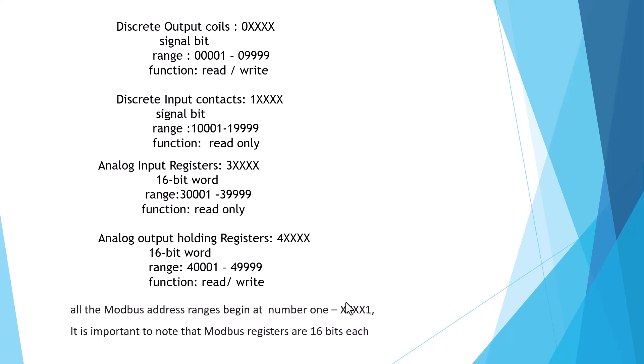Discrete output coil memory starts at zero. We use a four-digit number — it is single bit, ranging from 0001 to 09999. The function is read and write. Discrete input contact is a digital input only. Its memory starts at one, also a four-digit single bit number, ranging from 10001 to 19999. The function is read only — you cannot write.